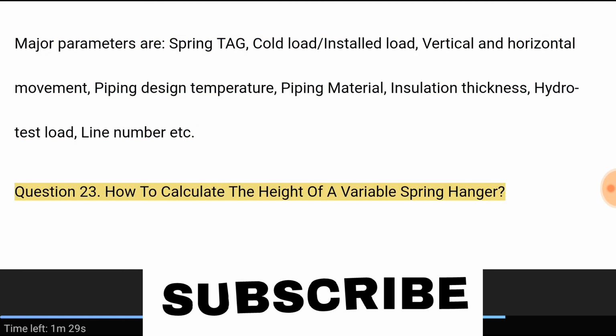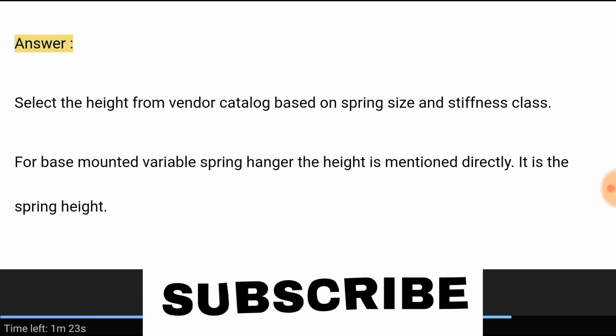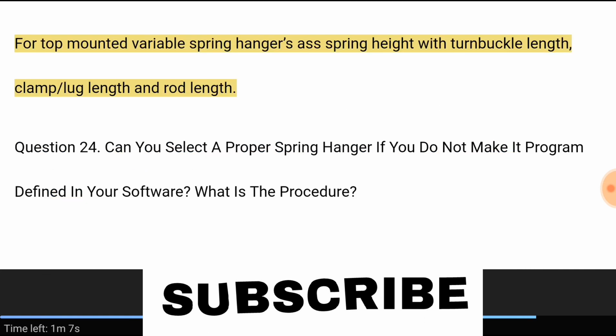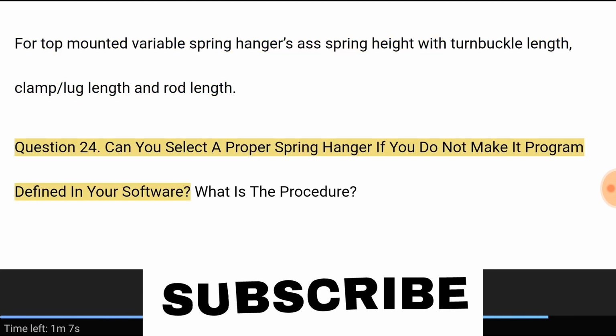Question 23. How to calculate the height of a variable spring hanger? Answer. Select the height from the vendor catalog based on spring size and stiffness class. For a base-mounted variable spring hanger, the height is mentioned directly. It is the spring height. For top-mounted variable spring hangers, add spring height with turnbuckle length, clamp, lug length and rod length.